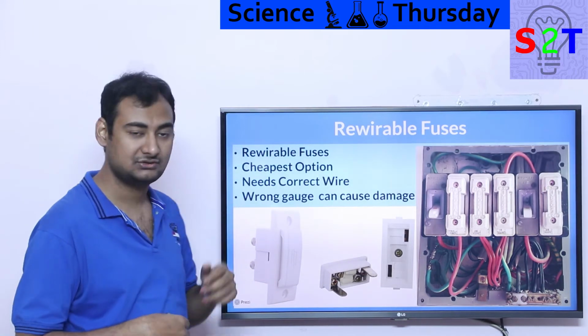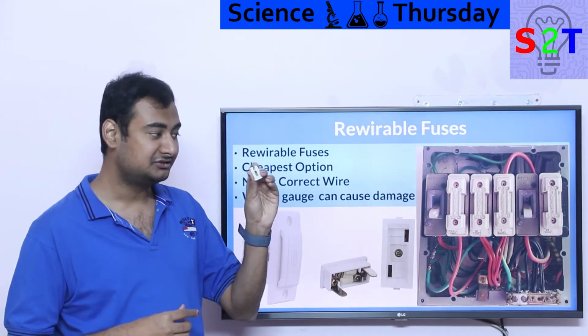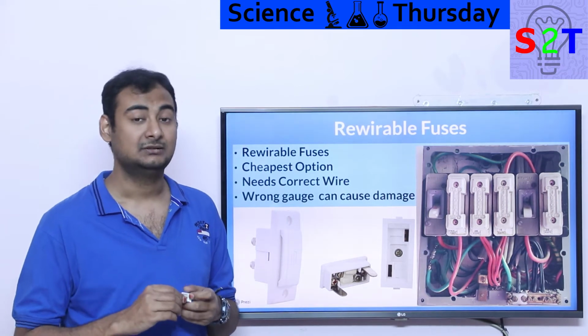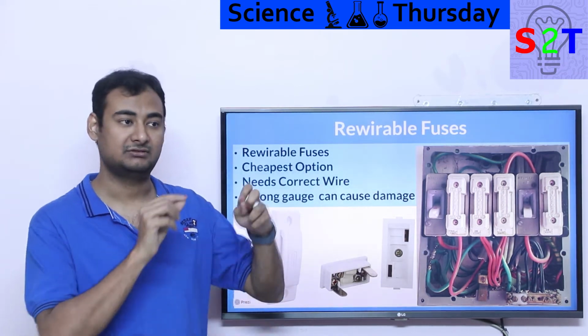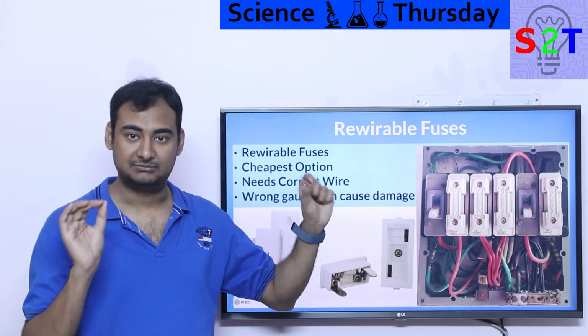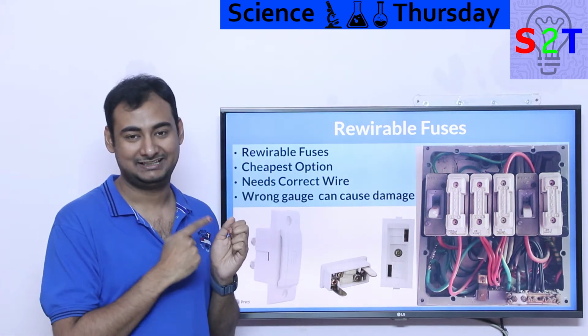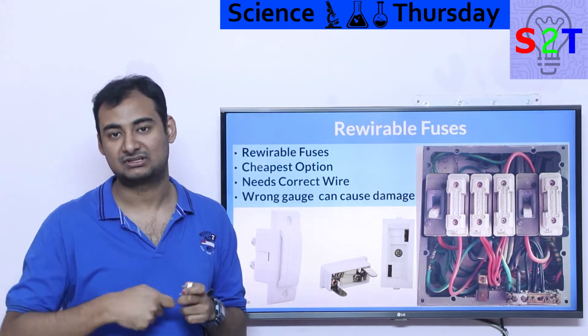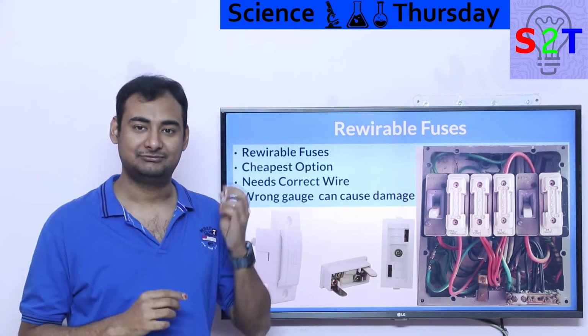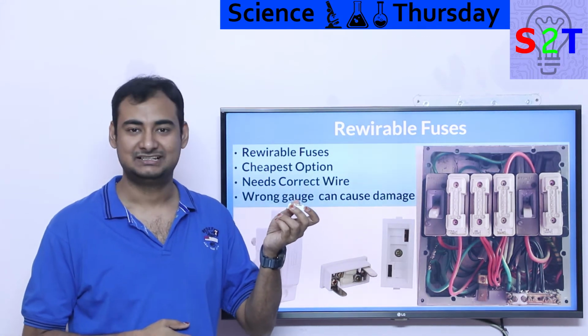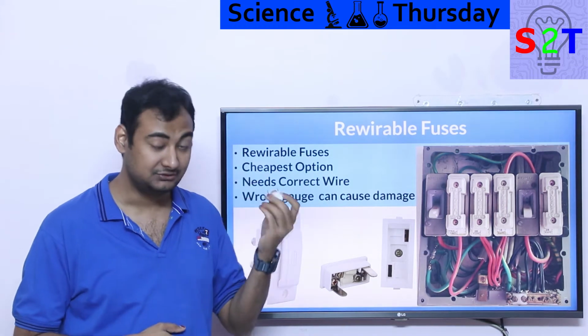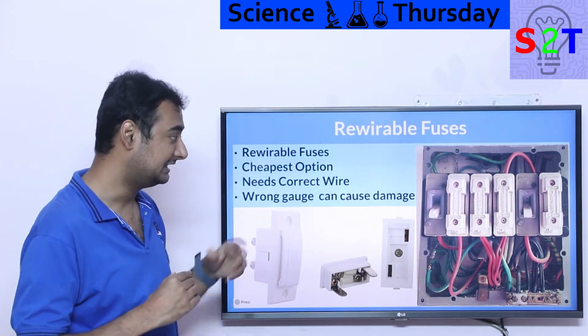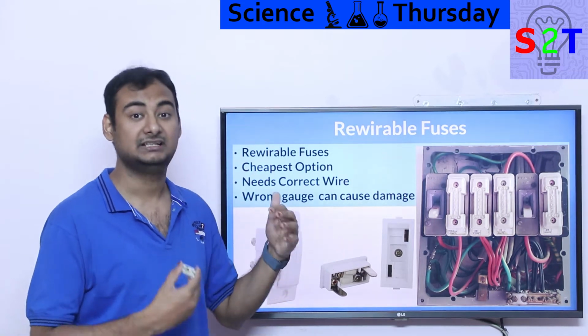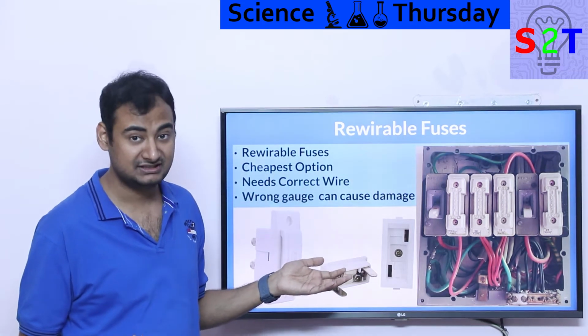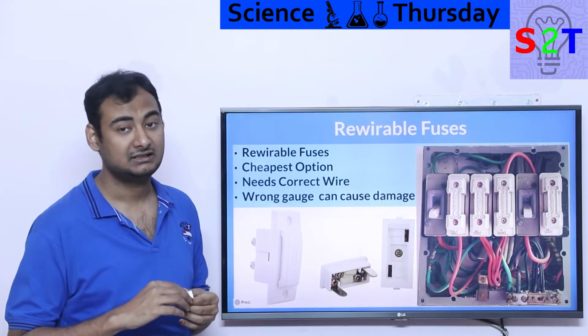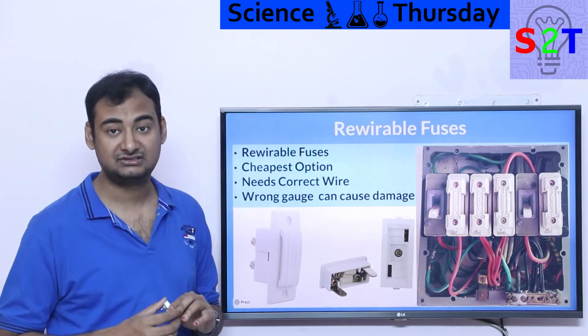So if you have a wrong gauge of system, it will cause damage. Will it trip if you have very high currents? Yes, but if you mess it up, let's say you have 2.5 square copper cable in your household, and your fuse wire, because you got so pissed off by having short circuits every time, you made it 3 by spooling it up. The fuse is the last thing that's gonna melt, the first thing that's gonna melt is the wiring. So the fuse must be weaker than the wiring inside. That is why these things, while they do work and are reliable, and we've been using them for almost a century, create a problem where they are ambiguous. So wrong gauges are very problematic.